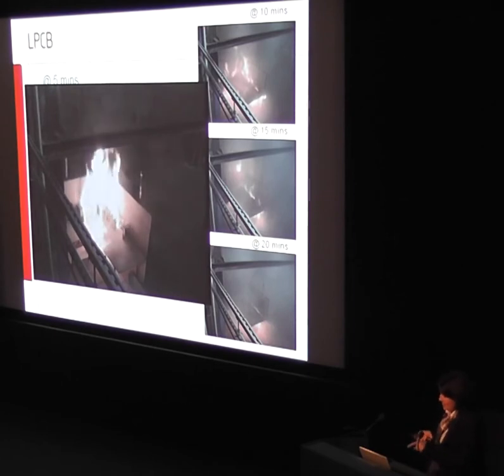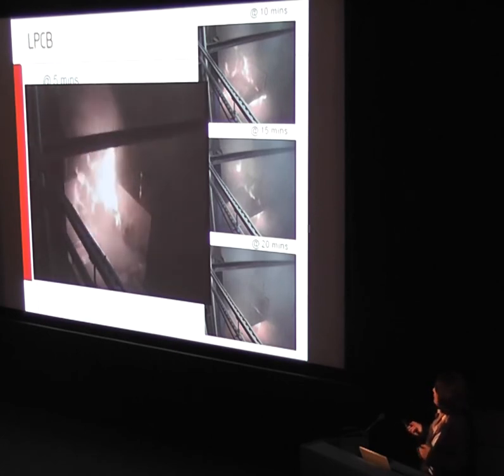So this is the high pressure system. I'm just going to show you the 5 minutes. 5 minutes was quite consistent for all the tests, the time of operation of the mist system. So this is at 5 minutes with the fire burning underneath, and this burning really triggered by the fire load under the table.